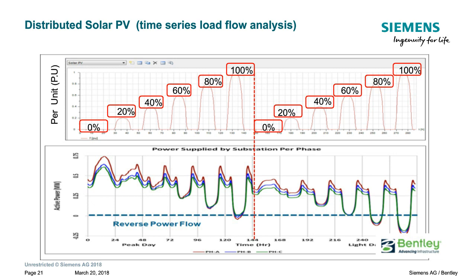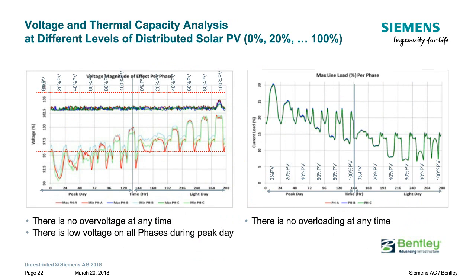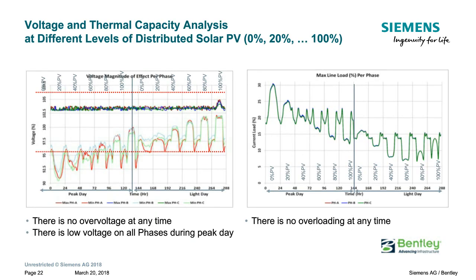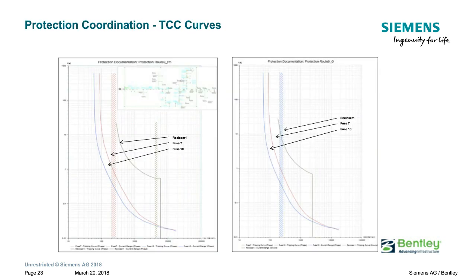Here are the voltage and thermal results. On the left is peak load condition and on the right is light load condition. On peak load, we see some low voltage problems. On the light load side, there is no voltage issue. On the thermal side, as more PV is added, we don't see thermal violations. Additionally, most utilities have overcurrent settings, fuse and recloser setups configured without DER, so when DER is interconnected, we must pay attention to whether relay and fuse coordination is maintained.